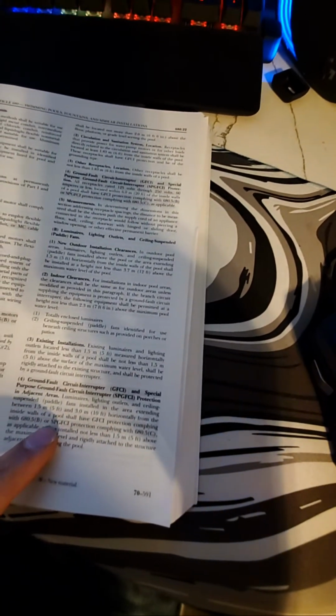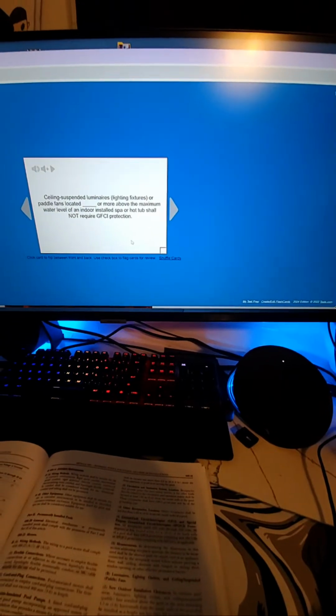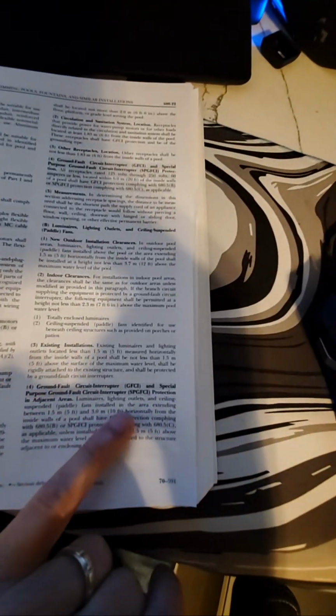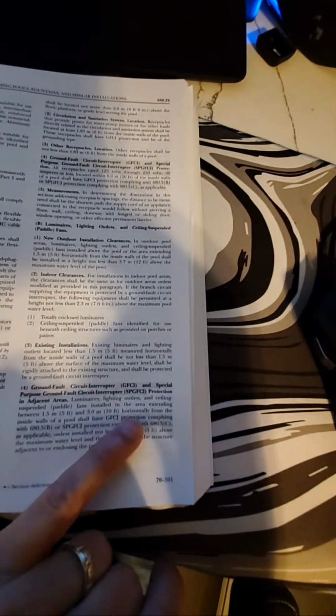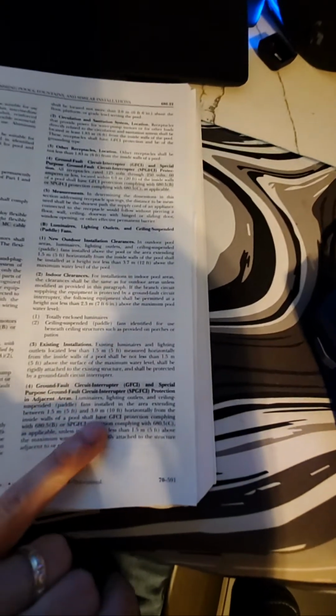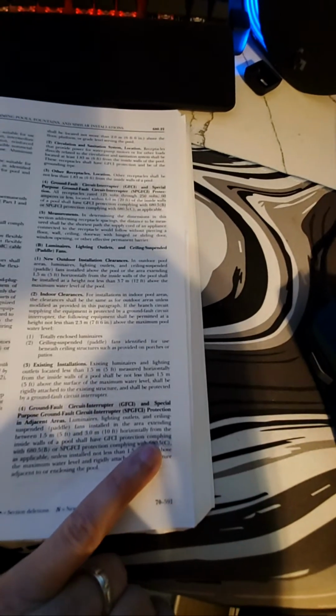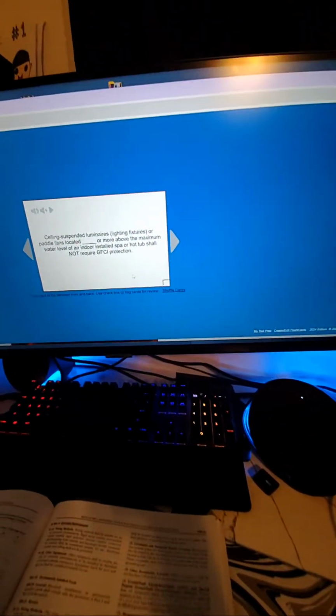Five feet. Oh my goodness. 5 feet and 10 feet horizontally from, is it horizontal or up? Maximum water level. So that's going to be up. Is it 10 feet? Let's keep looking. There's measurements, switching. No. Is it 10 feet? Luminaires, outlets, and ceiling fans installed in an area extending between 5 feet and 10 feet horizontally from the inside wall of the pool shall have GFCI protection. So if you're more than 5 feet, it should be 5 feet horizontally and 10 feet vertically, I thought.